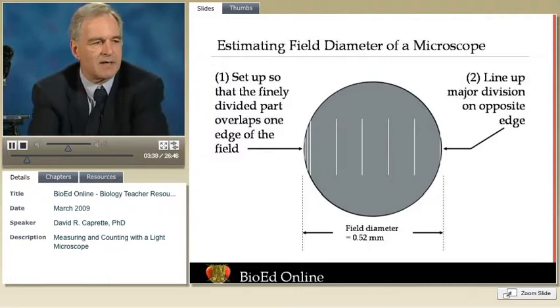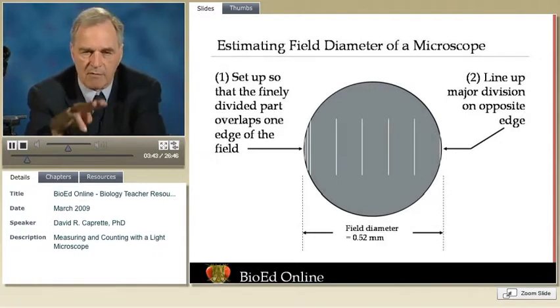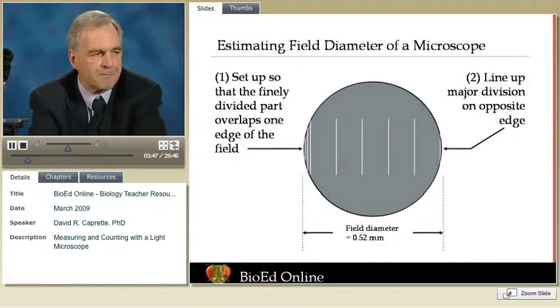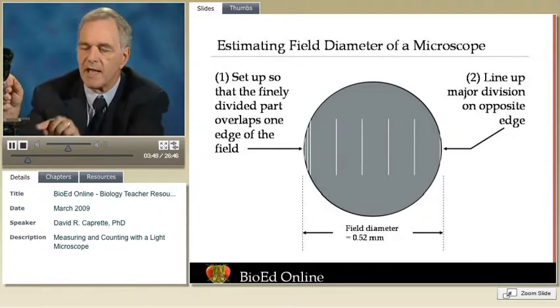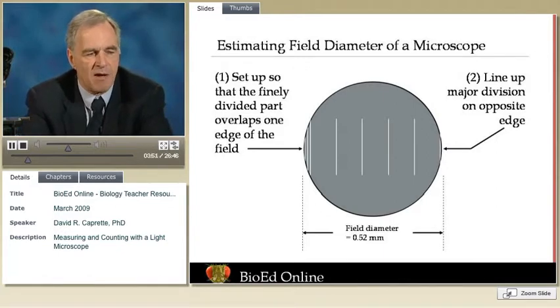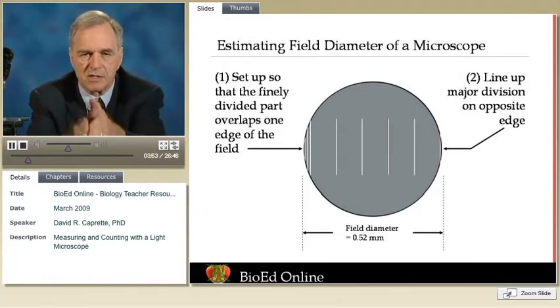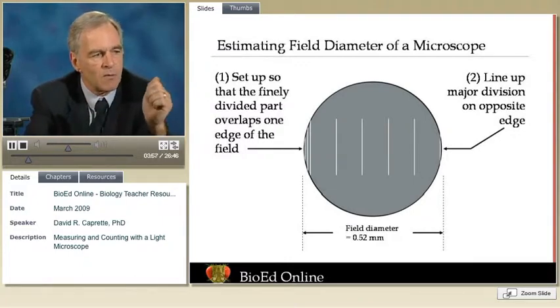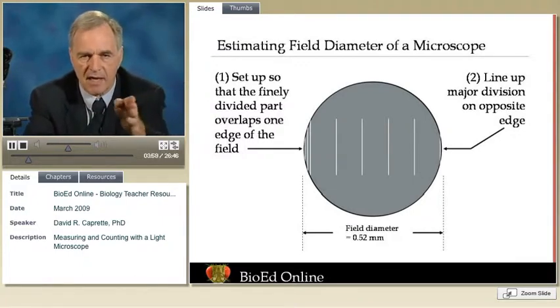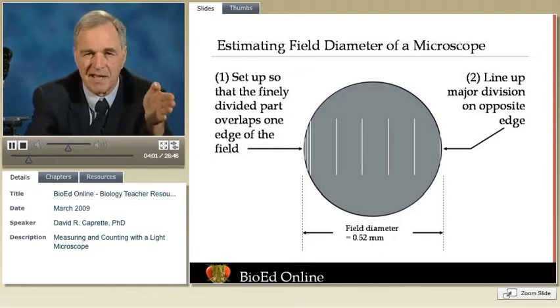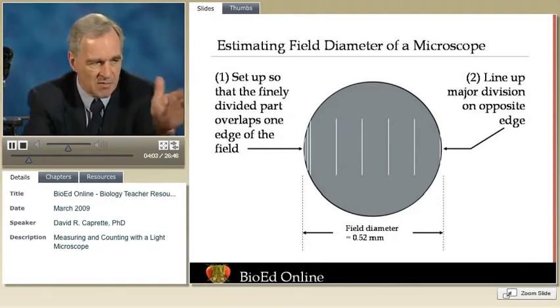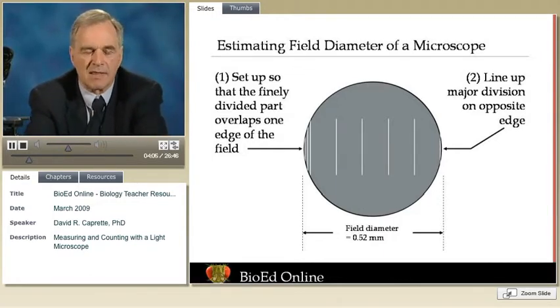It can even act as kind of a mini counting chamber, although we don't have a vertical dimension, we just have the XY plane. To estimate field diameter, we line up the stage micrometer so that one of the large divisions is at one side of the field, right on the edge. And then we make sure that the fine part of the scale, if there is one, overlaps the opposite side of the edge.